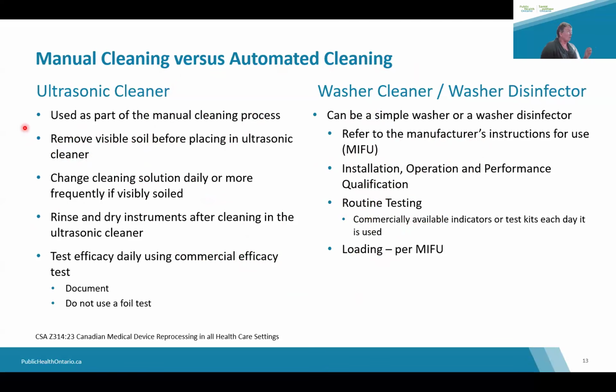If you're doing manual cleaning, you clean the instruments manually first in the sink, under the water, and then you're going to use an ultrasonic cleaner, but you have to remove all the visible soil before placing them into the ultrasonic cleaner. You're changing the solution daily or more frequently, because if it becomes cloudy, you need to change it. And as I said, you need to rinse and dry the instruments after they come out of the ultrasonic cleaner, and you need to test the ultrasonic cleaner for its efficacy using a commercial efficacy test. Document that you did the testing, as I'm sure you learned in school: if you don't document it, you didn't do it. And the foil test is no longer acceptable for testing the efficacy of an ultrasonic cleaner.